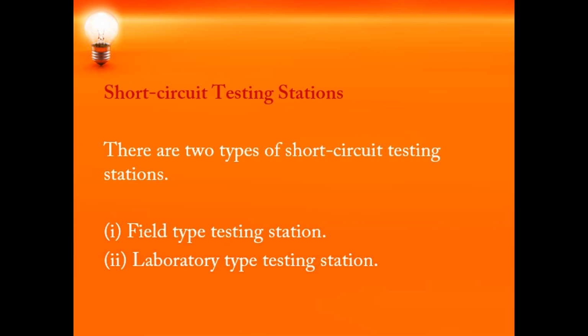But what will be the advantage? One thing I have already told you, you can test n number of times, okay, and you can have control over your restriking voltage, recovery voltage, current, everything. And you can carry out the testing of circuit breakers of any large capacity. So these are the advantages and disadvantages of field type and laboratory type testing stations.